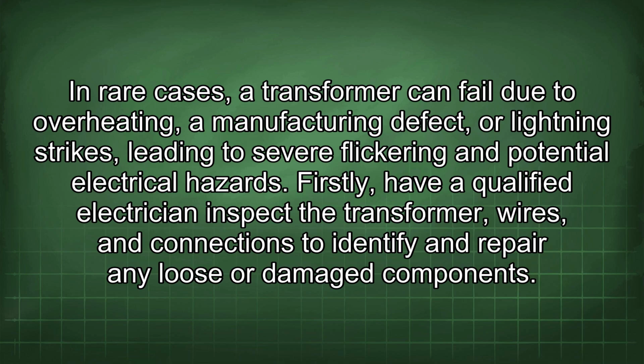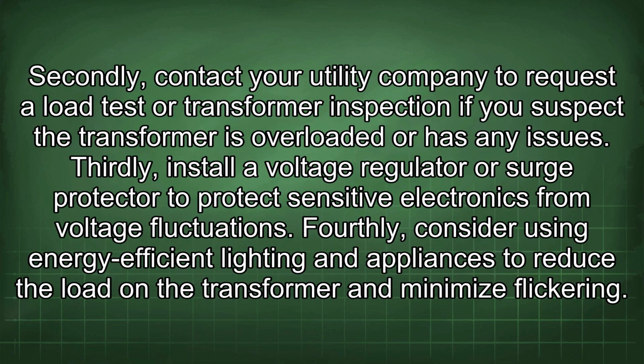loose or damaged components. Secondly, contact your utility company to request a load test or transformer inspection if you suspect the transformer is overloaded or has any issues. Thirdly, install a voltage regulator or surge protector to protect sensitive electronics from voltage fluctuations. Fourthly, consider using energy-efficient lighting and appliances to reduce the load on the transformer and minimize flickering.